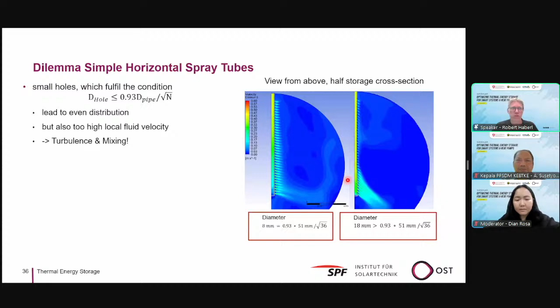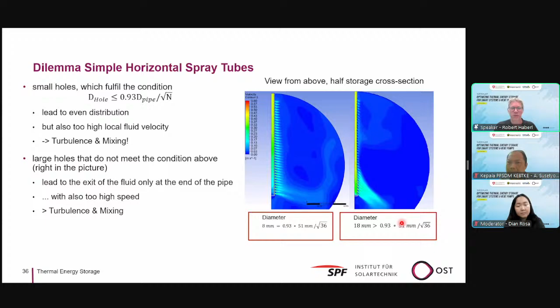you have high local fluid velocity, and that leads to turbulence and mixing. So I would not recommend that. You can do bigger holes to have a bigger overall surface where the water can enter the storage tank. But that leads to the exit of the fluid only at the end of the pipe, where the distance to the storage wall is short again, and that again has high speed at the end of the pipe and turbulence and mixing. So I couldn't recommend that either. So spray tubes are not a good solution, and maybe you should already forget about that solution and not use it.